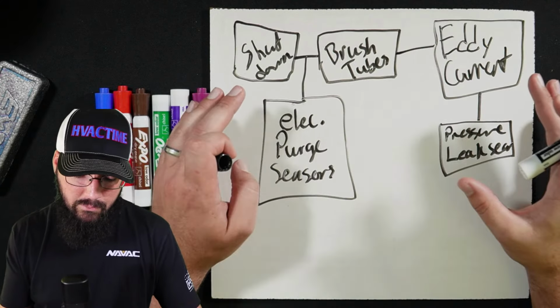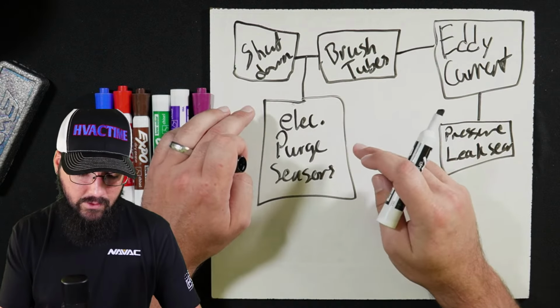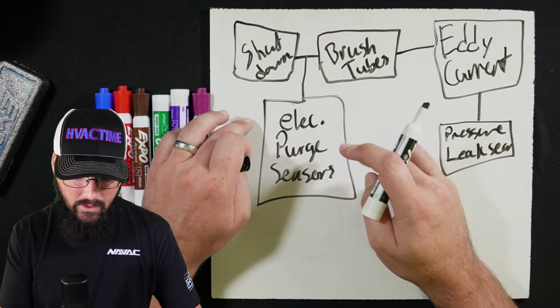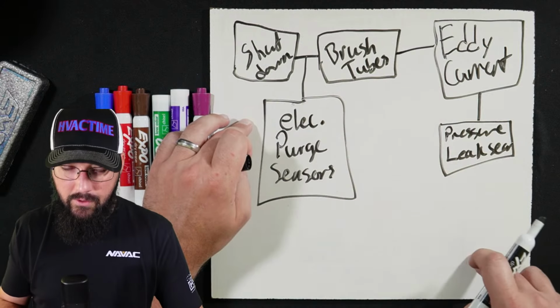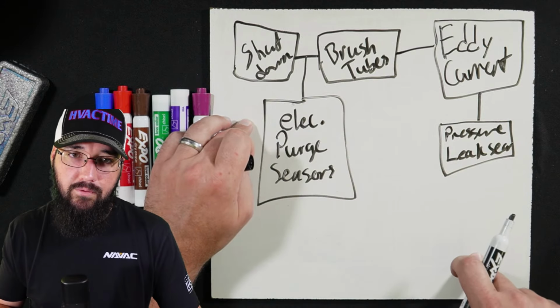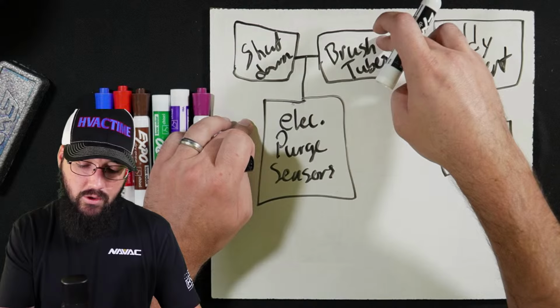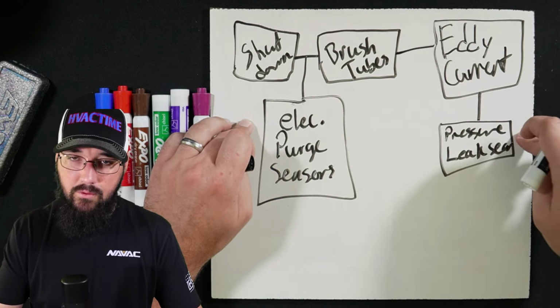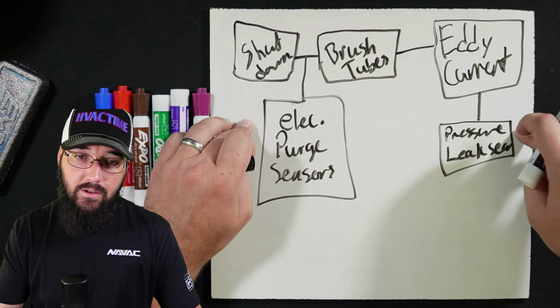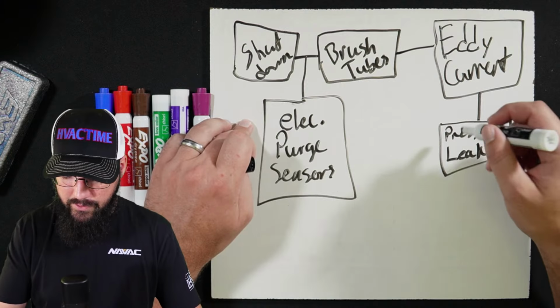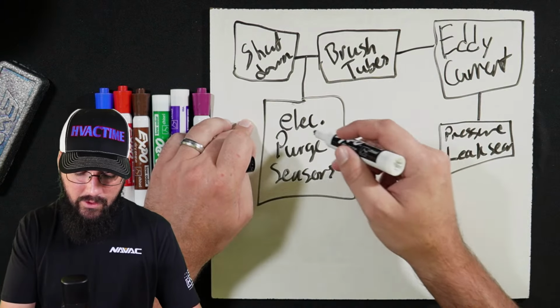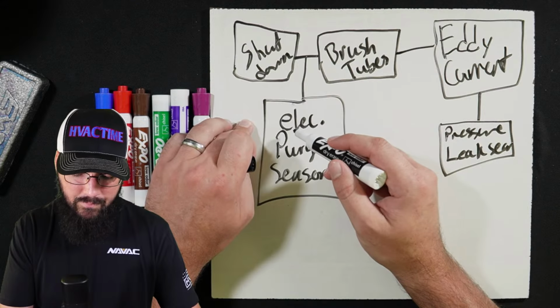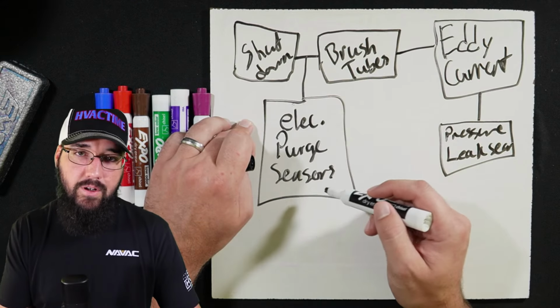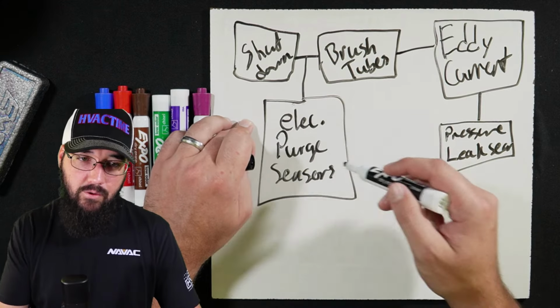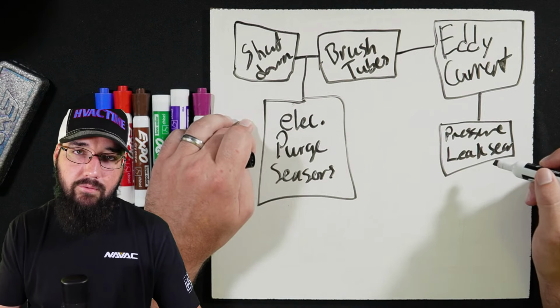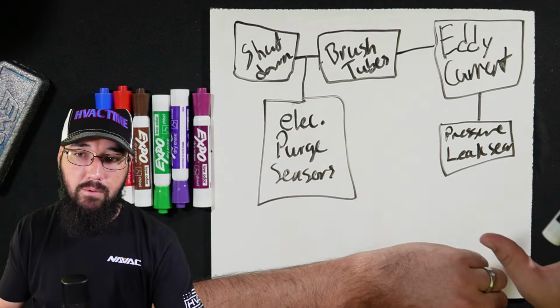If this was a 1-man process, I usually insert this later into the workflow. So I'll start with tubes, eddy current, pressurizing and leak search, and then after we do the leak search, I would probably do the electrical purge and sensors. That would be a good time to do that after we finish the leak search process, if I was doing this by myself.